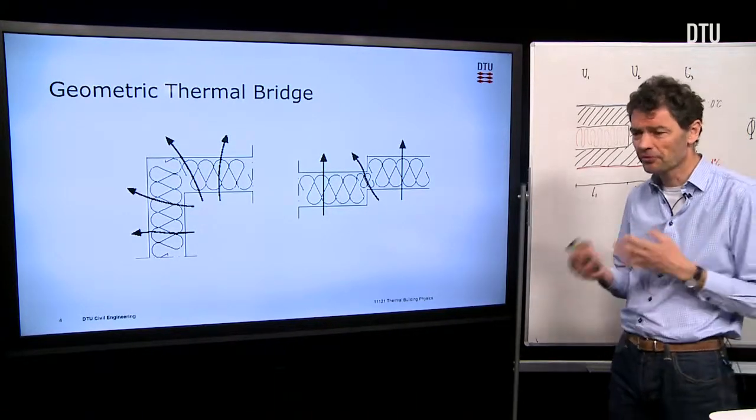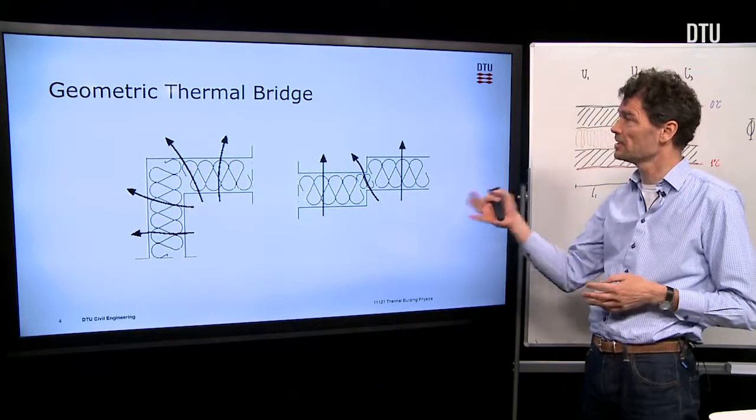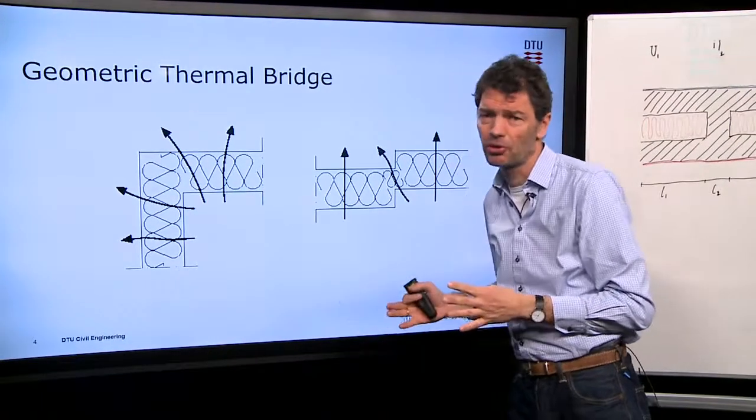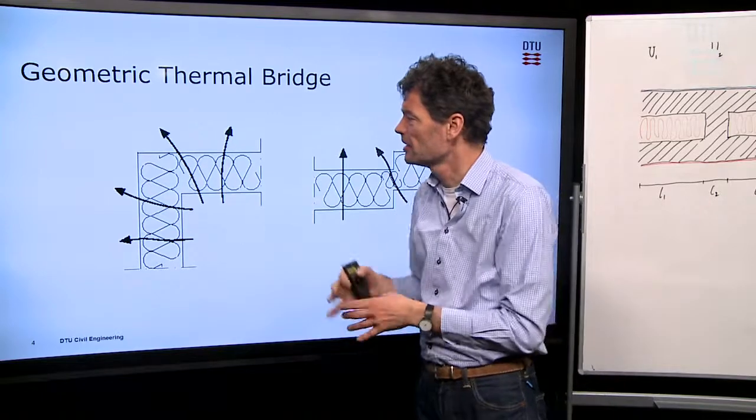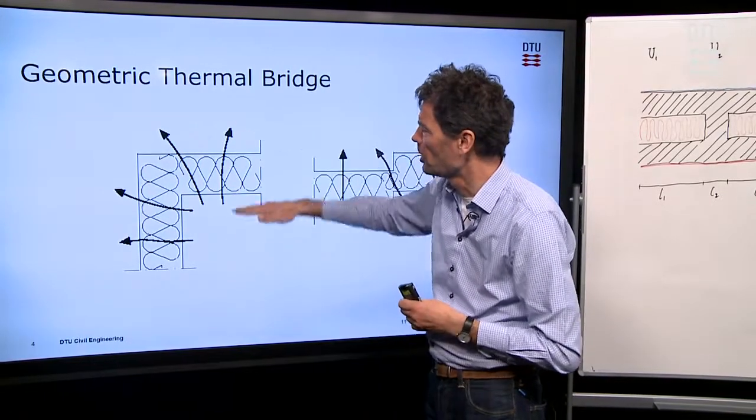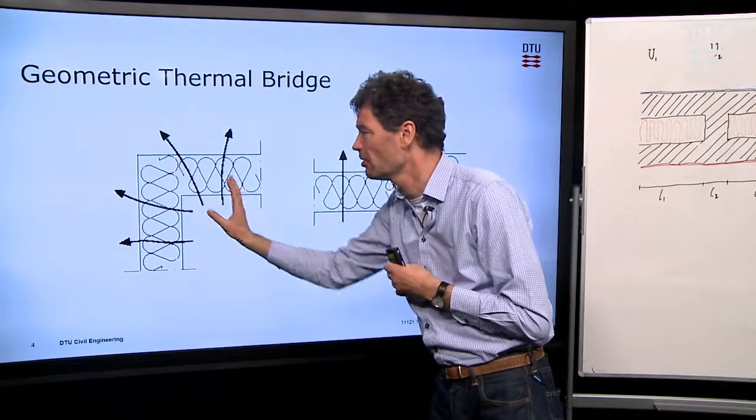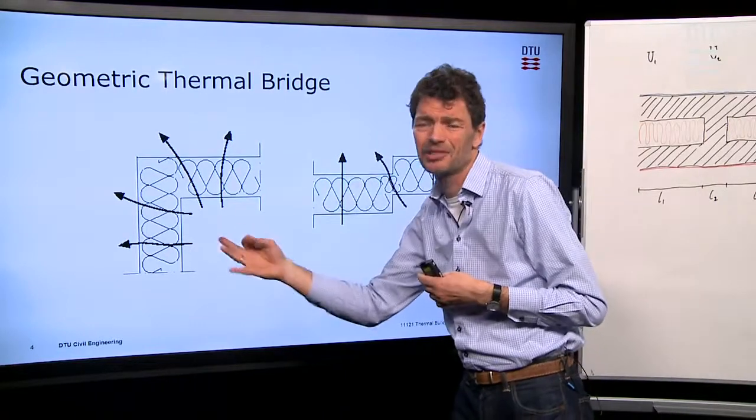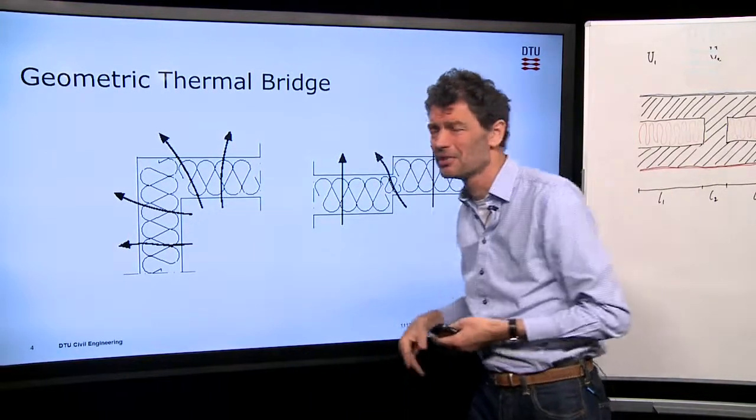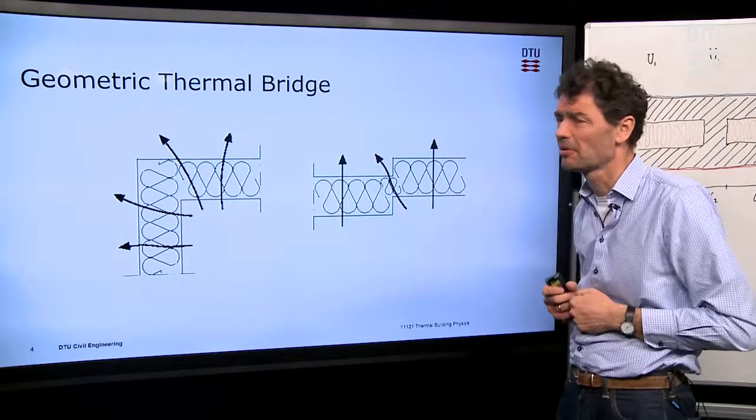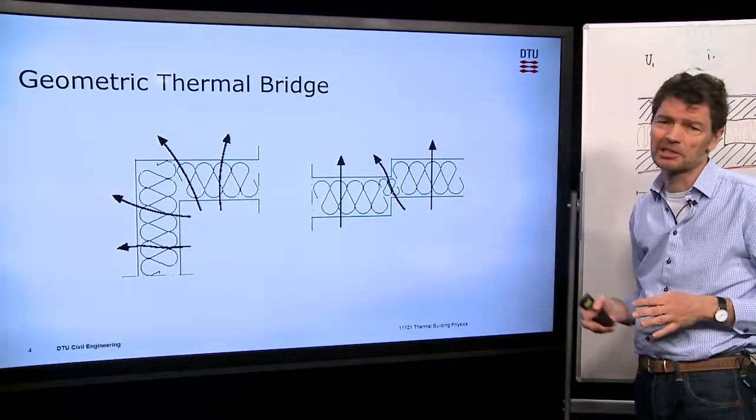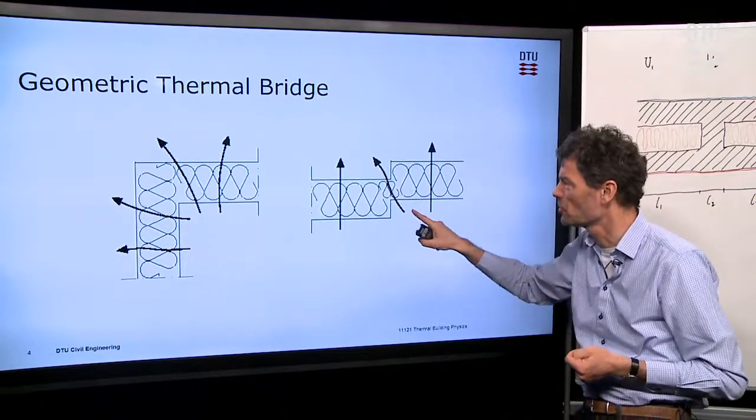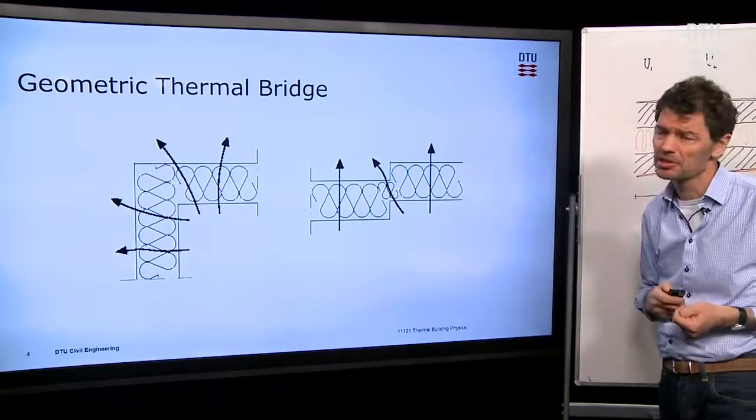There are four types of thermal bridge as we normally look upon it. The first type is the geometrical thermal bridge. Here it's the same material that passes around the corner of a building, but just the fact that the heat flow can go one-dimensionally through some part of the wall, but as it comes close to the corner, the heat will also have a possibility to take the path through the corner itself, and that leads to an extra heat loss.